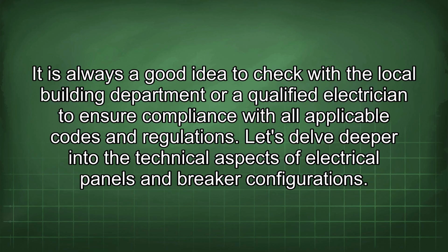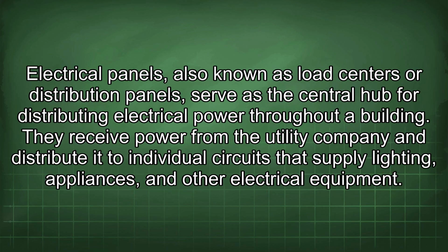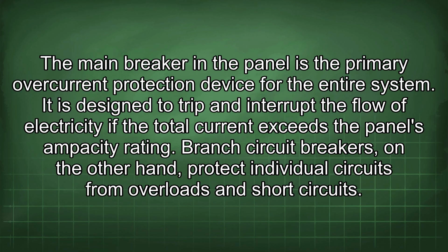Let's delve deeper into the technical aspects of electrical panels and breaker configurations. Electrical panels, also known as load centers or distribution panels, serve as a central hub for distributing electrical power throughout a building. They receive power from the utility company and distribute it to individual circuits that supply lighting, appliances, and other electrical equipment. The main breaker in the panel is the primary overcurrent protection device for the entire system. It is designed to trip and interrupt the flow of electricity if the total current exceeds the panel's ampacity rating.